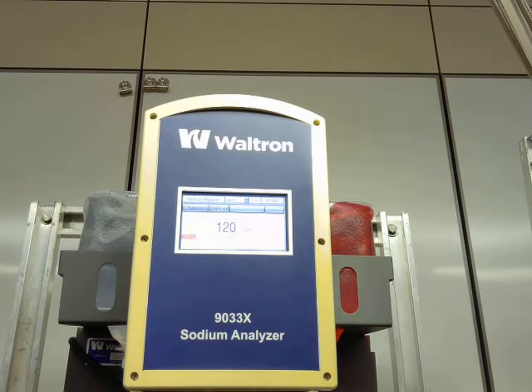Like I was saying, the analyzer is always online, always running. Once you hit that cal button, it will hold the 4 to 20 output, so you won't see your calibration standards come through on your DCS. And like Joe was talking about, you have that hold period at the end of the calibration as well, to allow your analyzer to rinse back down from that high standard before making that 4 to 20 live again.